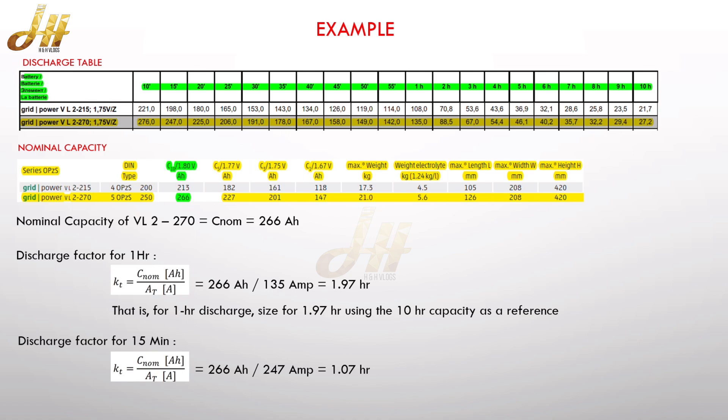As we said earlier, we will go for another example. In this case, I am going with another model number VL2-270. The nominal capacity of this battery is 266 Ah. So how we can calculate the discharge factor for one hour? We can take this value from the above chart, which is 135 ampere. So if you divide 266 Ah divided by 135, which is equal to 1.97.